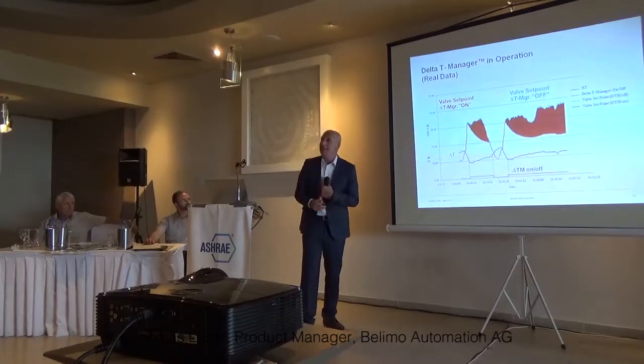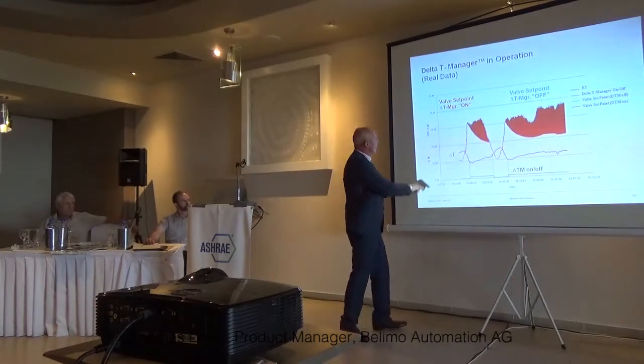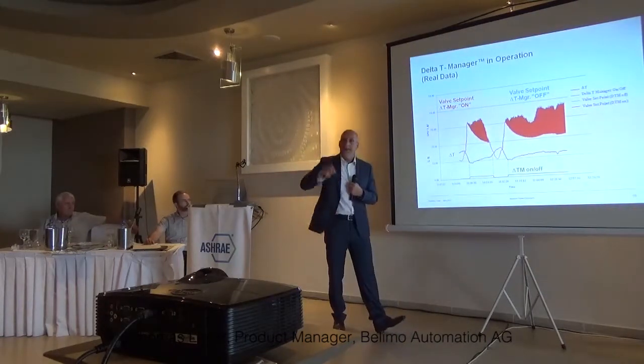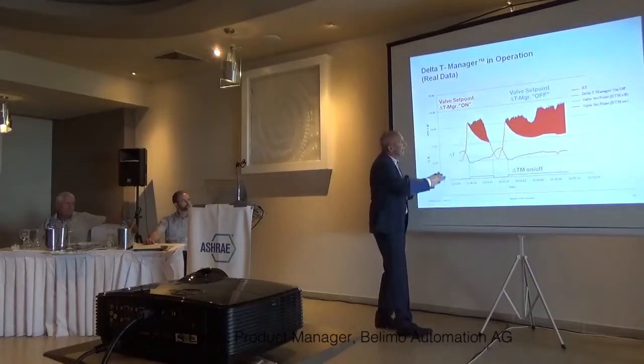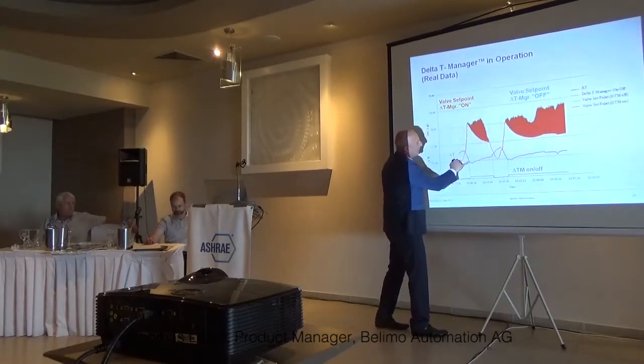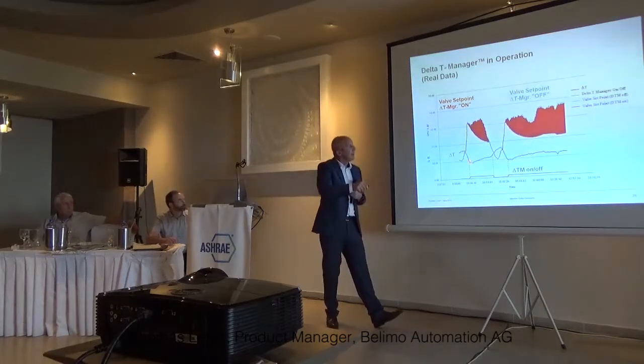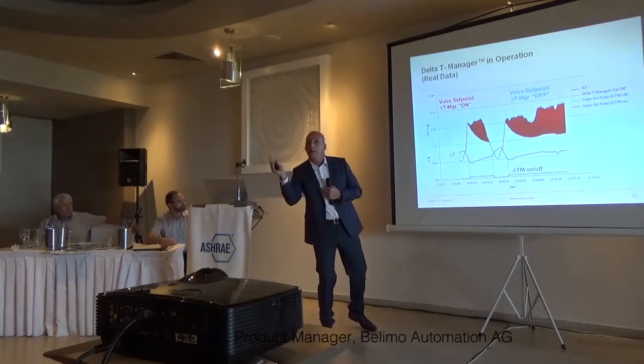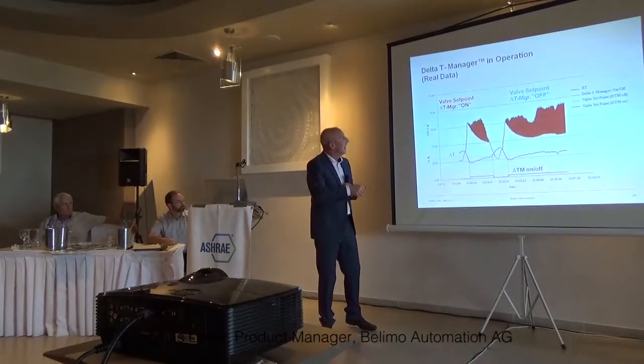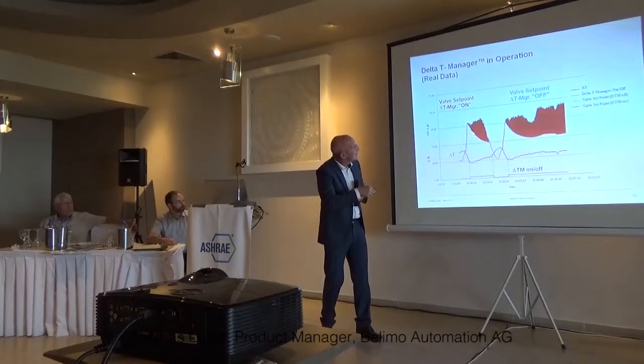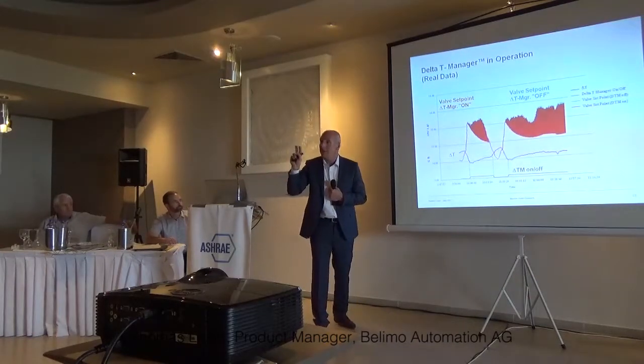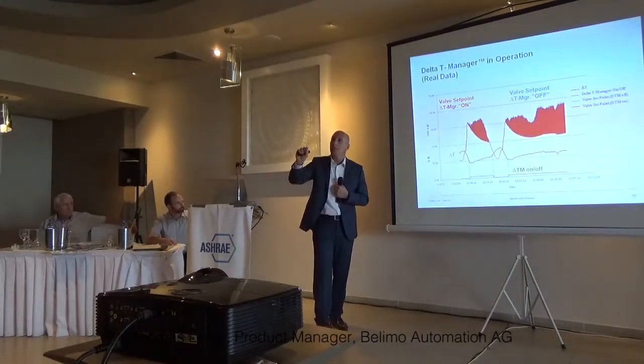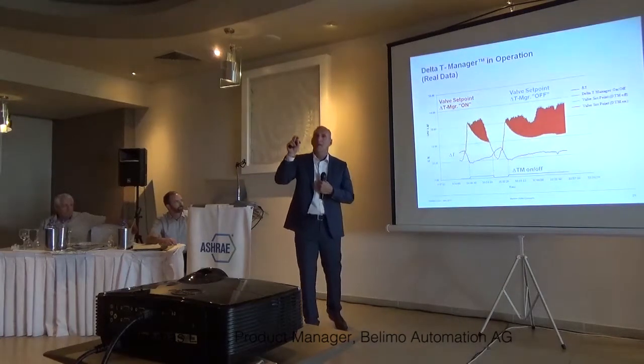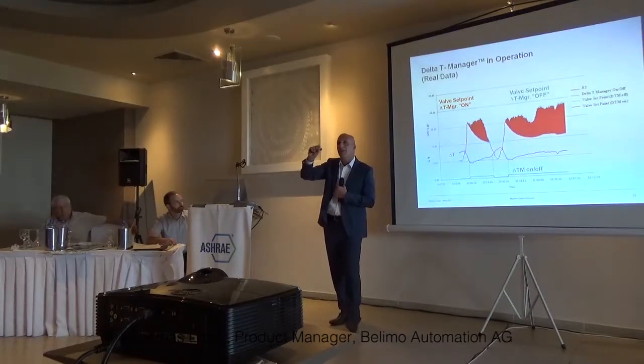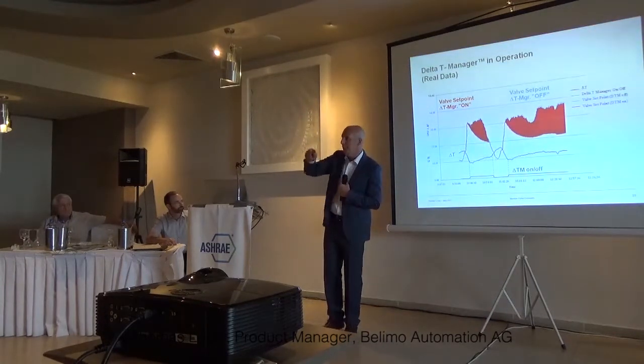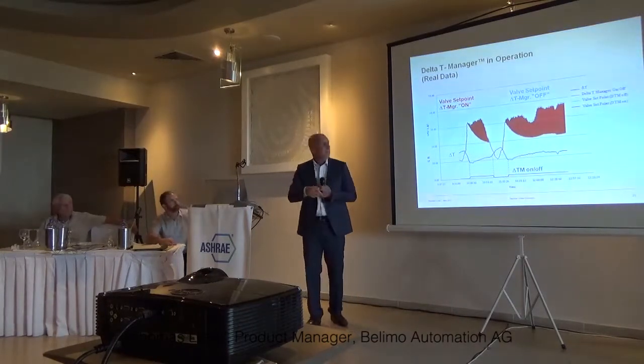What it actually leads to is a curve that looks like this. Here this is my delta T that I want to maintain. This is a set point that comes. Here my set point is rising. At that moment my valve will realize that at this point the delta T is too small, and then it will reduce the flow gently to just keep the delta T. We are focusing here on delta T, so that it can be maintained. A valve focusing on maintaining the desired delta T. Of course, this delta T can also be set through the parameters.